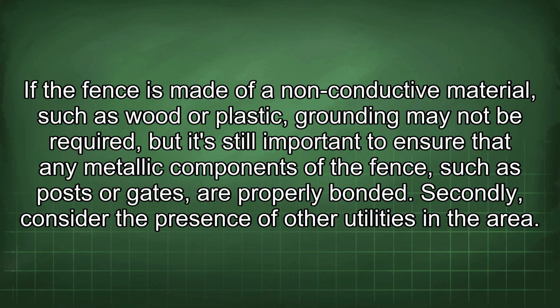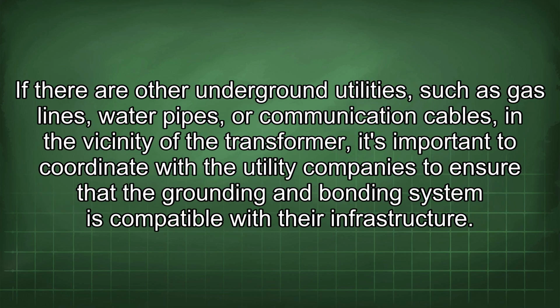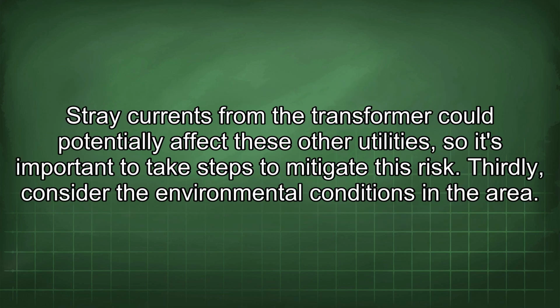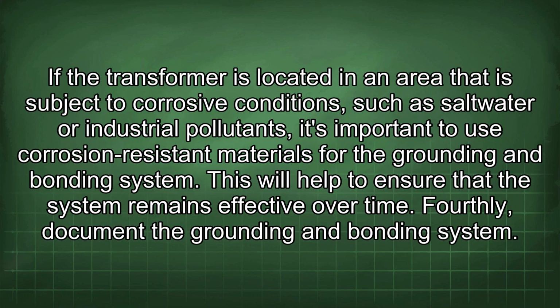Secondly, consider the presence of other utilities in the area. If there are other underground utilities, such as gas lines, water pipes, or communication cables in the vicinity of the transformer, it's important to coordinate with the utility companies to ensure that the grounding and bonding system is compatible with their infrastructure. Stray currents from the transformer could potentially affect these other utilities, so it's important to take steps to mitigate this risk. Thirdly, consider the environmental conditions in the area. If the transformer is located in an area that is subject to corrosive conditions, such as saltwater or industrial pollutants, it's important to use corrosion-resistant materials for the grounding and bonding system. This will help to ensure that the system remains effective over time.